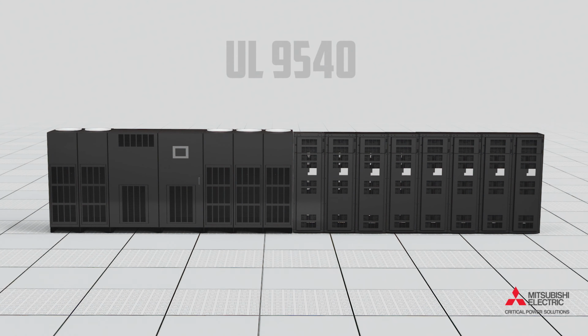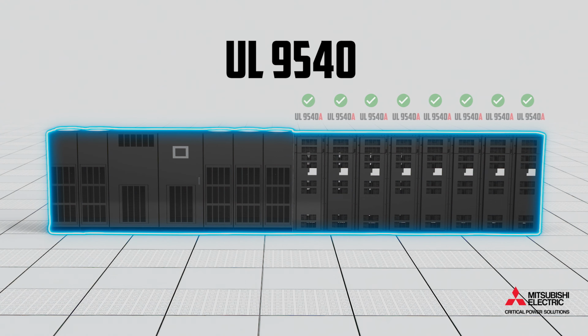For a UPS system to receive UL 9540 listing, it requires testing, validation, and verification by UL, or a UL nationally recognized and approved testing agency. Remember, the key to this is that UPS and DC technologies are tested, validated, and verified together as an energy storage system. The DC technology should have been tested, approved results to UL 9540A, if applicable, and be UL listed to appropriate standards and listings, such as UL 1973, a required listing for many batteries and DC technologies.